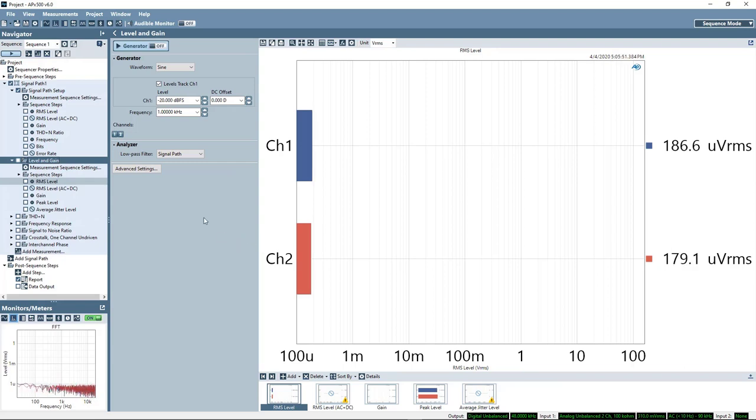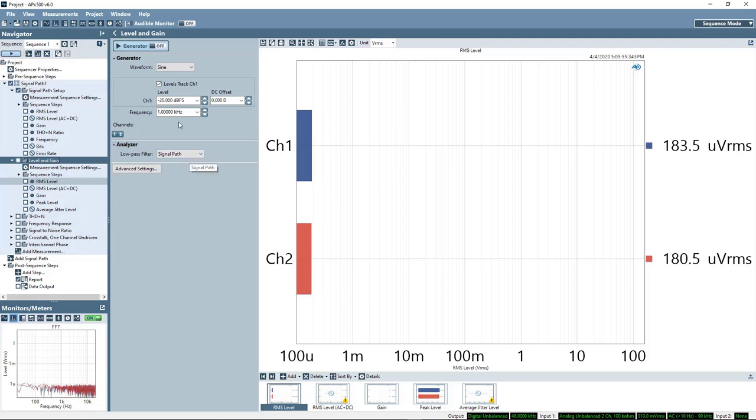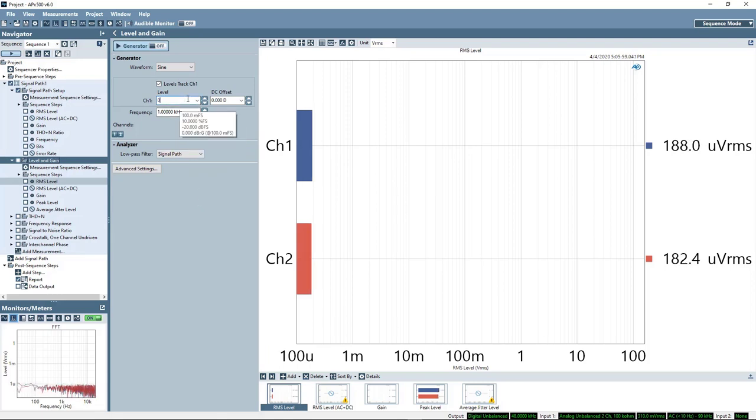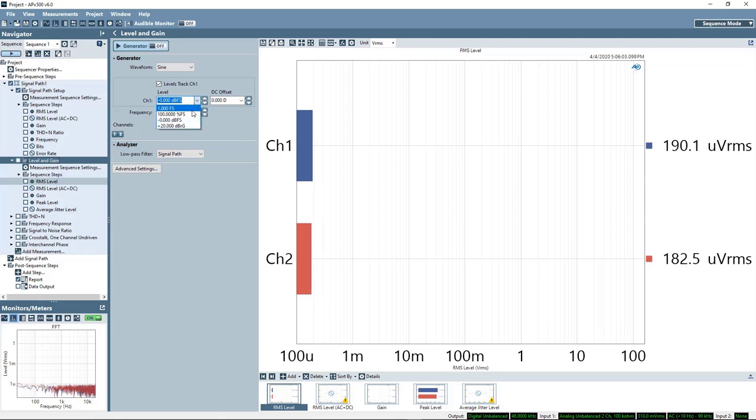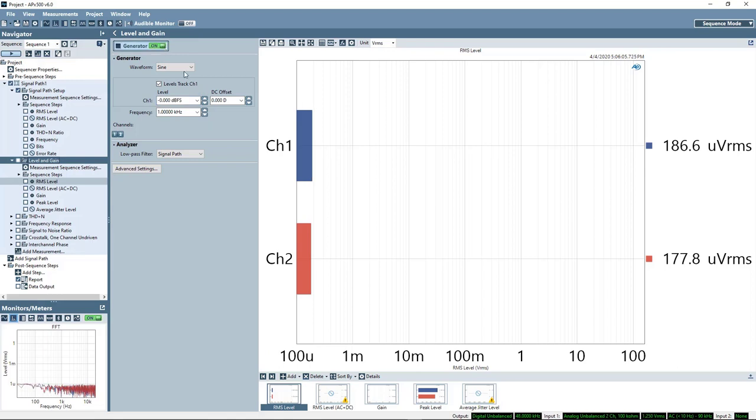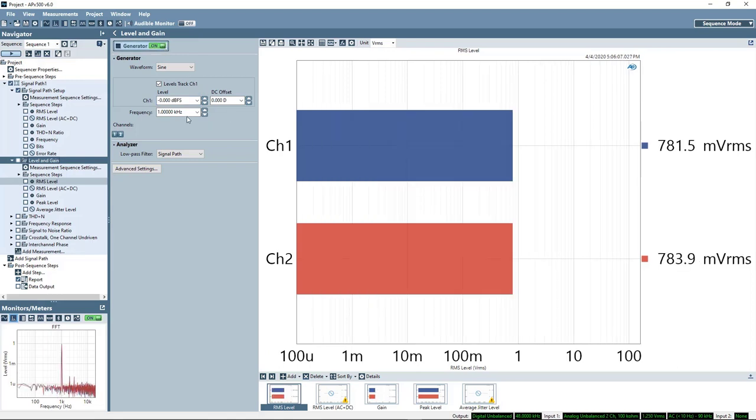Here we just want to see what is the output level of the device for given digital input. I'll do this test at full scale, 0 dBFS or 1FS if you prefer. I can turn the generator on.